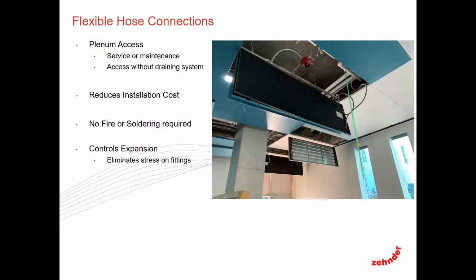Now, this is important because one, during installation, and then two, once the system's up and installed and operating, it allows the facility and maintenance engineers to get in there and not have to drop the entire loop out. So you don't have to drain the system, close it, isolate it, refill it. This allows you to get up into that plenum space, not have to worry about taking the hose off or draining that system. So it's flexibility and access into the plenum.